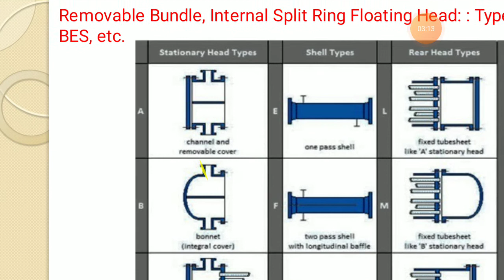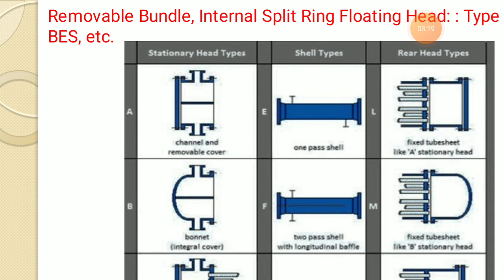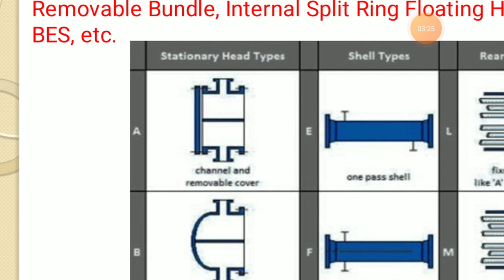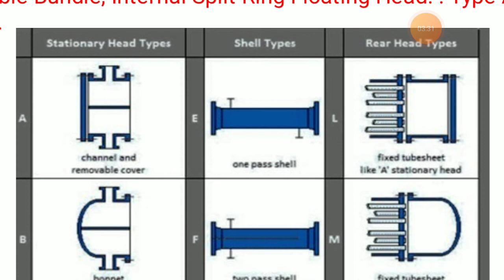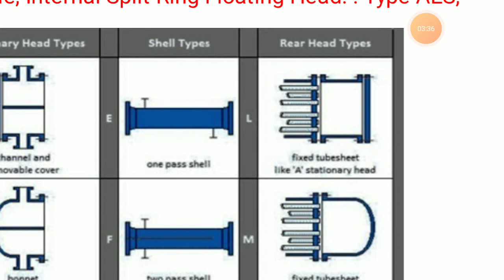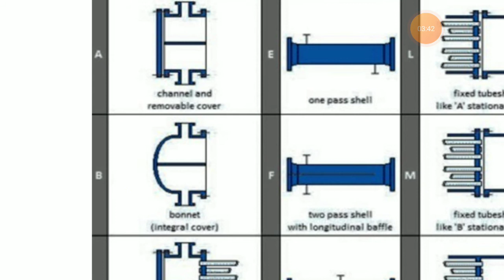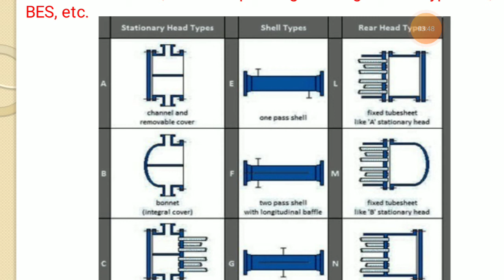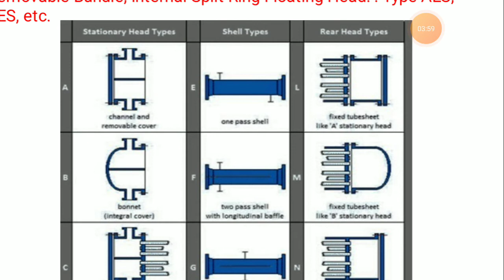So there are different types. A, the first one, is the stationary head type, channel and removable cover. This is the TEMA standard which is generally used. E stands for shell type, a one pass shell, which is shown here, AEL, and L is the rear head type, that is fixed tube sheet like A stationary head. Second one, bonnet. This bonnet is generally used for stationary head type, which includes an integral cover. Shell F is a two pass shell with longitudinal baffle, and fixed tube sheet like B stationary head.